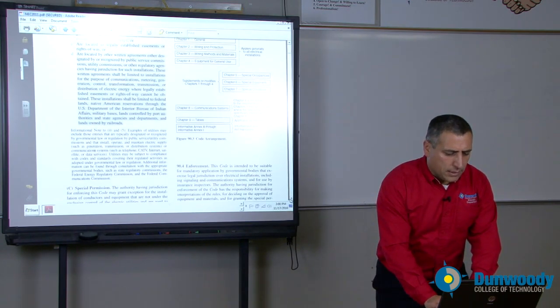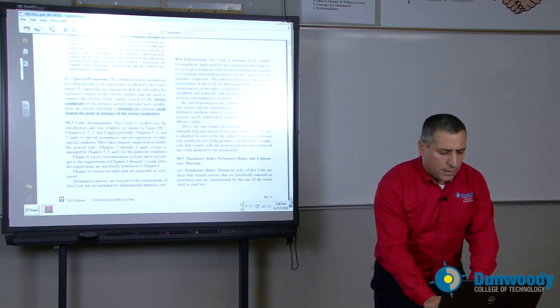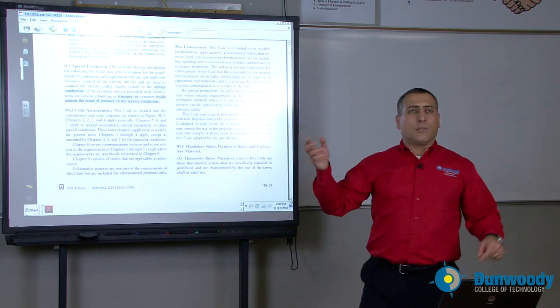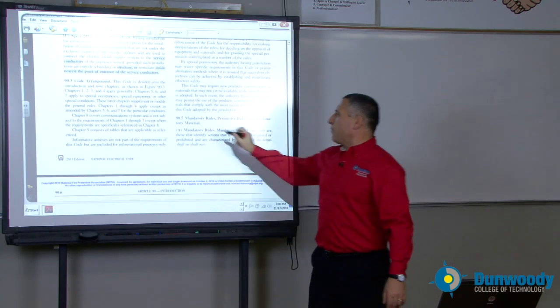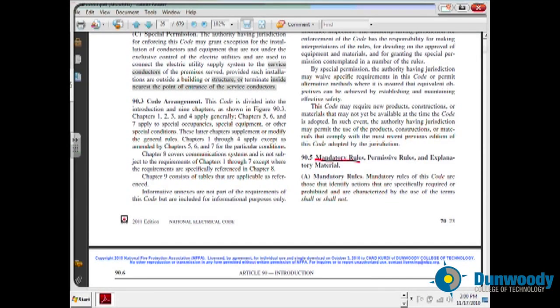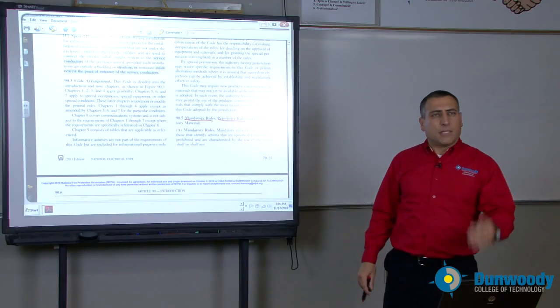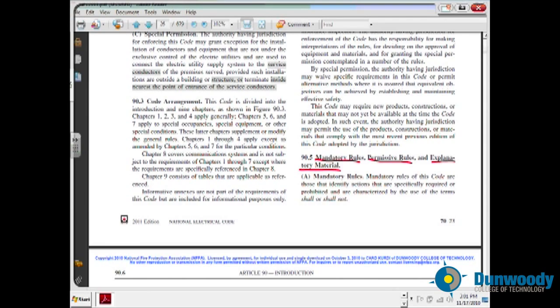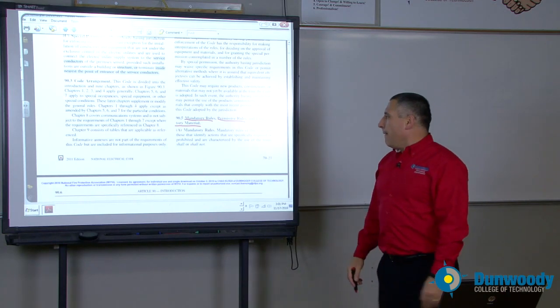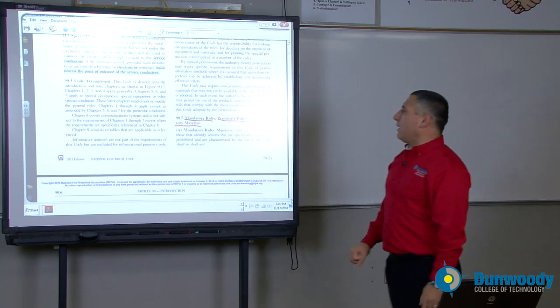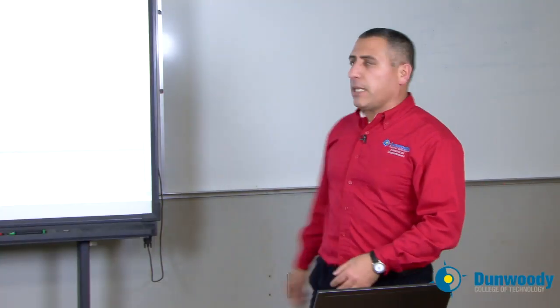Legally required items and enforcement — who enforces the NEC codebook? The authority having jurisdiction: the government that we elect on the local or state level. In the NEC codebook there are mandatory rules, permissive rules, and explanatory rules. Certain things start with 'shall' — you must do it. Permissive means 'shall be permitted' — it's up to you to do it. Explanatory material, like the 3% voltage drop recommendation, is informational. You don't have to do it. So these are the important distinctions between mandatory, permissive, and explanatory rules.